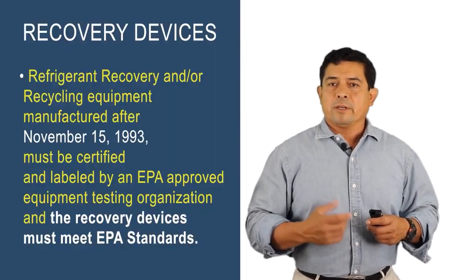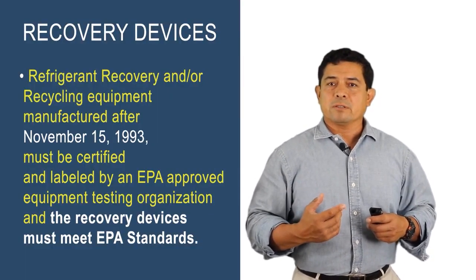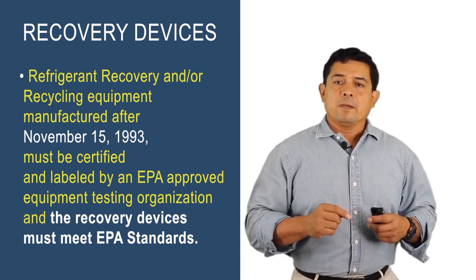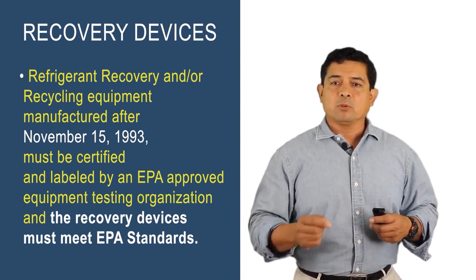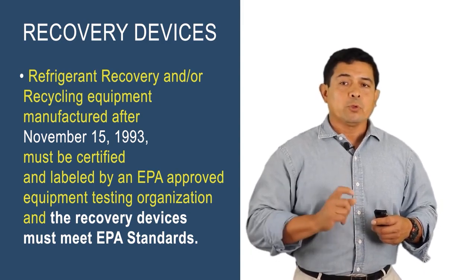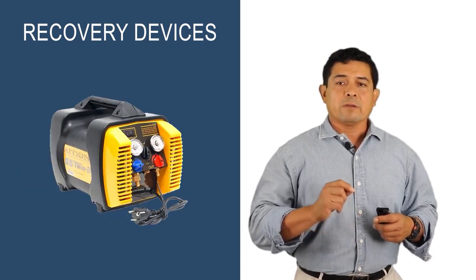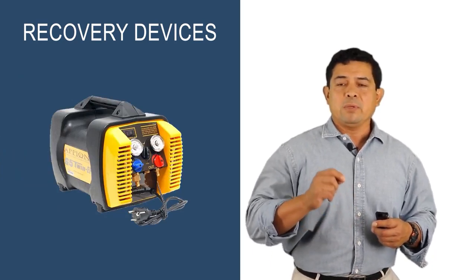Now we said you're going to recover the refrigerant. When you recover it, you have to have a recovery machine. Refrigerant recovery machines or recycle equipment manufactured after November 15th, 1993 must be certified and labeled by an EPA approved equipment testing organization, and the recovery device must meet EPA standards.